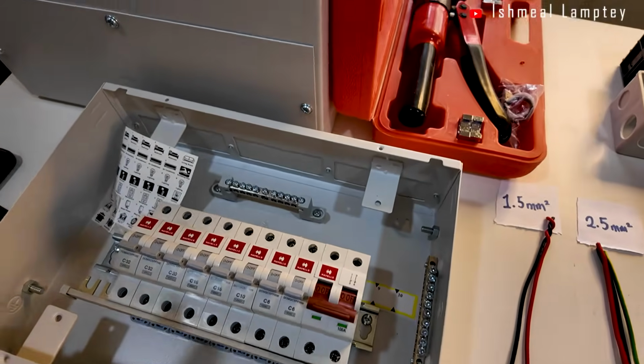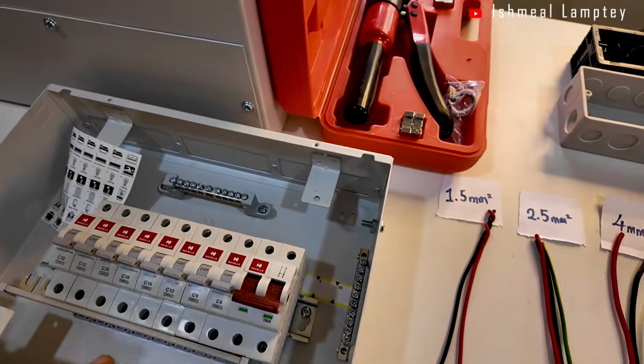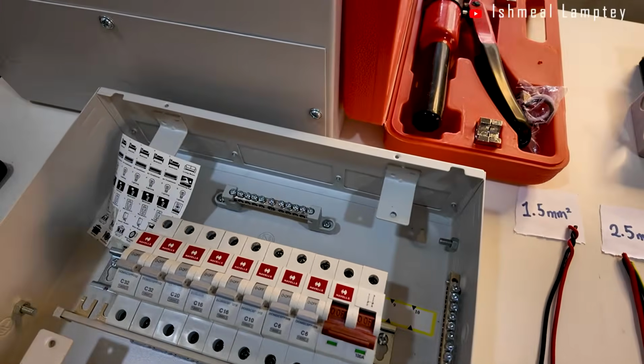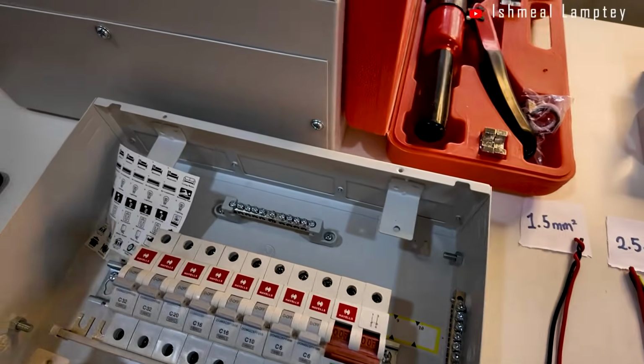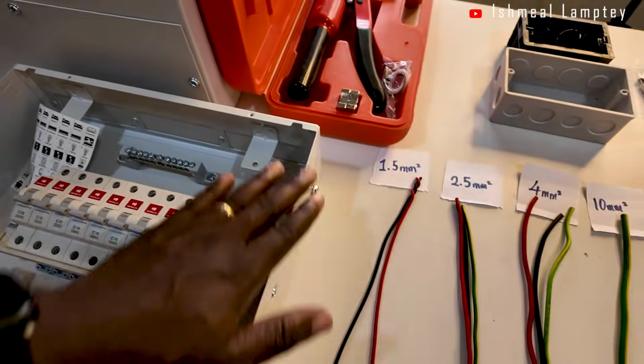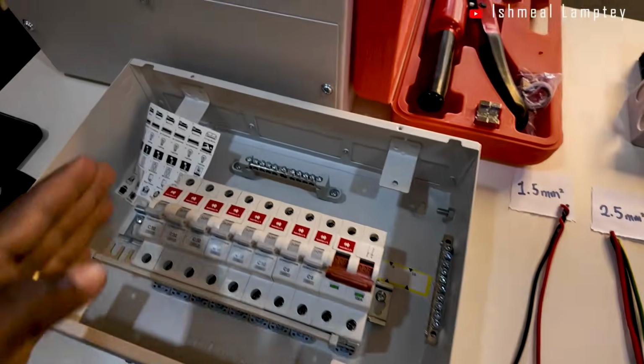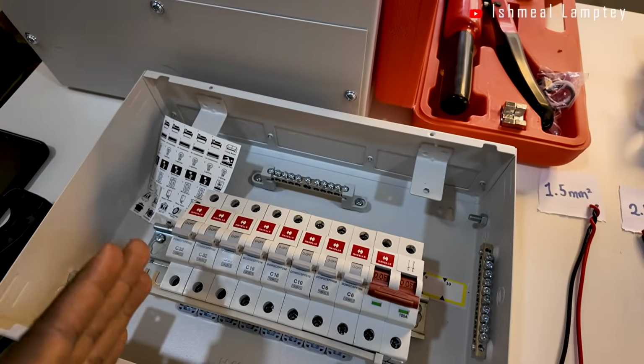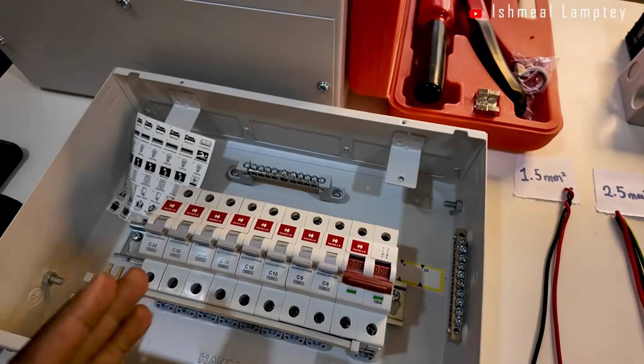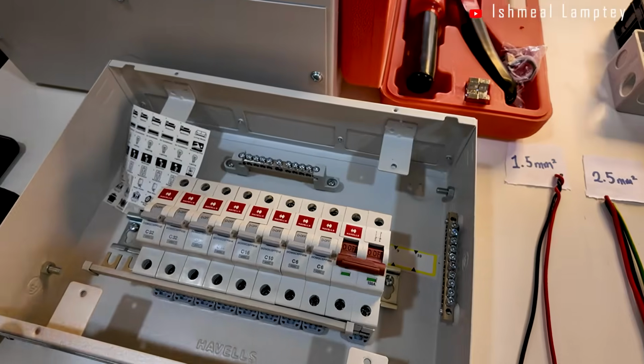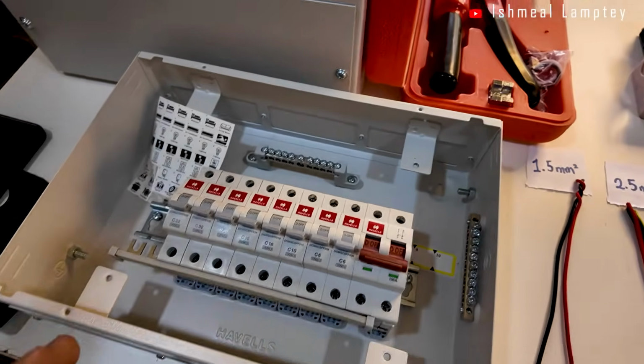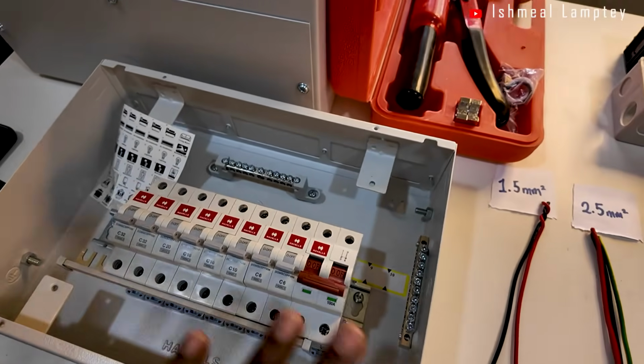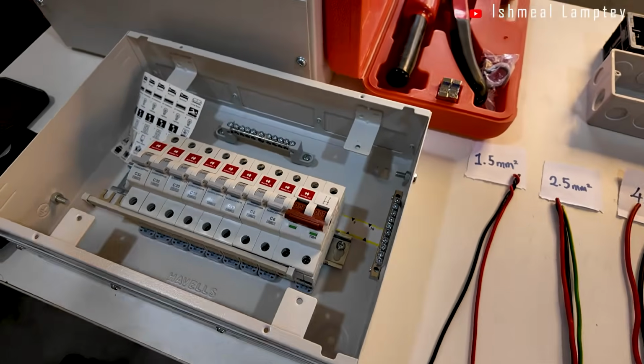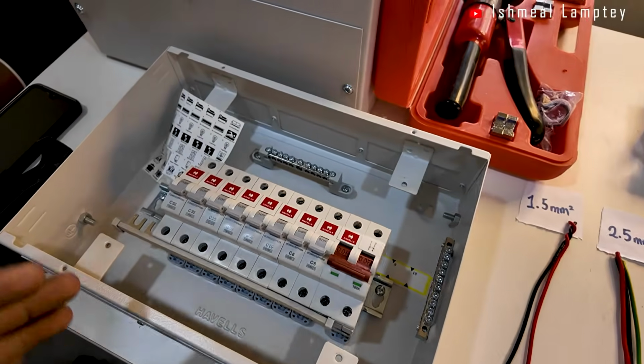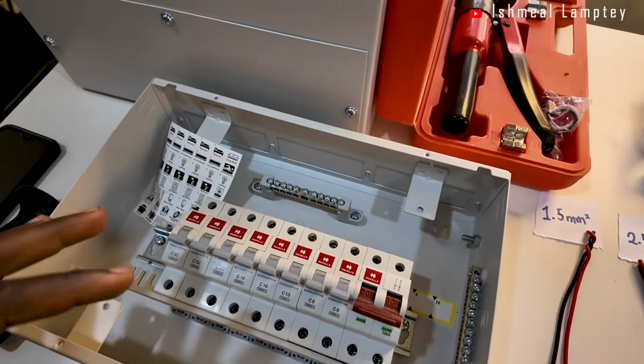If it's a 3-phase system, you have 3 of whatever ways you have. So if it's 8-way, that's 8 times 3. If it's 12-way, 12 times 3. This means you'll have a bigger panel with a lot of breakers in it, with each of the 3 live lines having its own dedicated breakers, among others. That's the basic concept of a single phase versus a three-phase system.